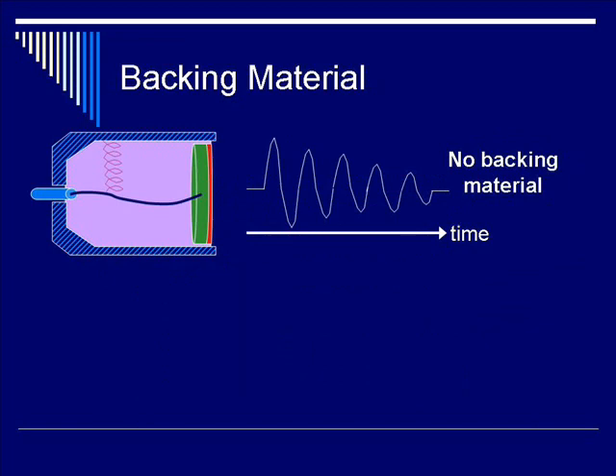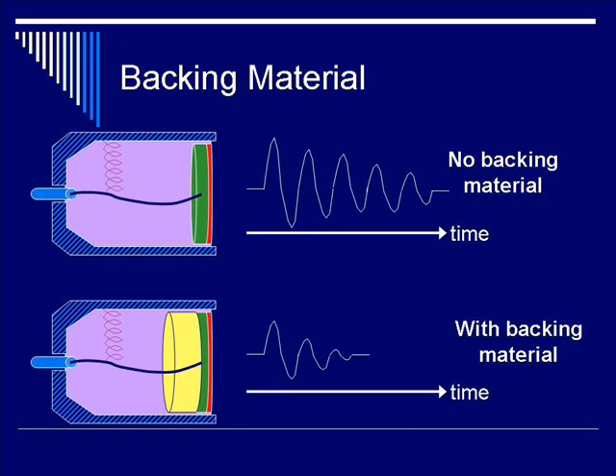Here's a cartoon of an ultrasound output with no backing material. If you add this yellow thick layer behind the transducer element, with the backing material, you have significantly reduced pulse duration, as shown with the decreased ringing. And that is desirable.